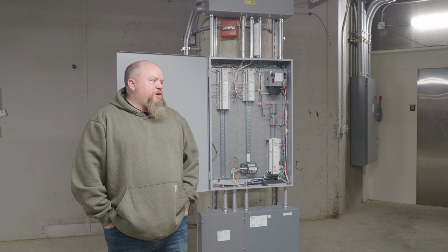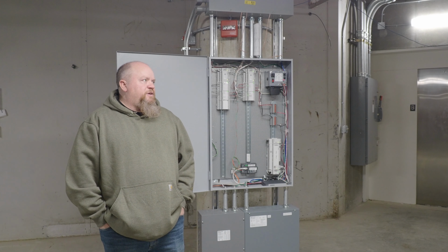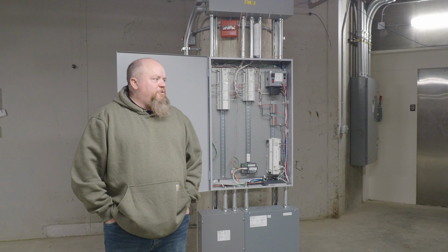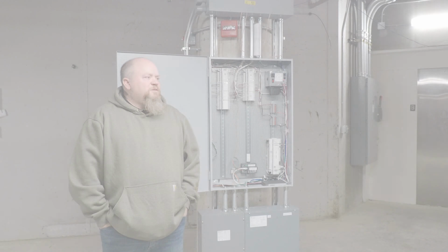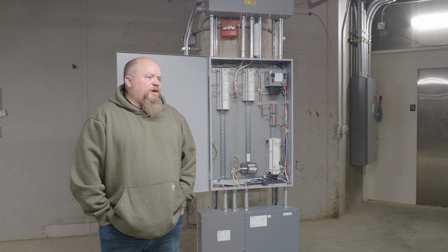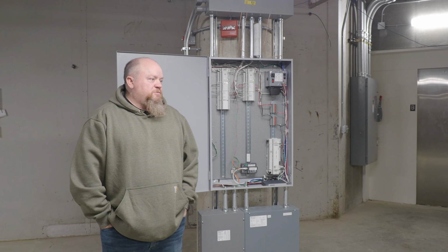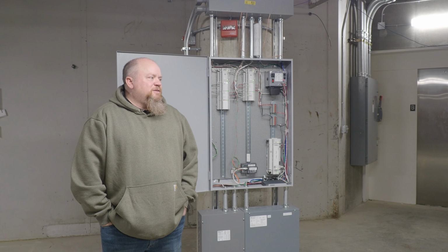Now you probably have some areas, I don't know about some of the fan coils and such. There are old fan coils that they didn't touch that have no controls because they were pneumatically controlled, and you have no air in the building anymore. There are several of those in the building. At some point you're going to want to figure out how to make those work, because they have pneumatic air valves. We have no pneumatics, so the valve is going to be wide open year round on those, and they will get heat because you can't turn the loops off.